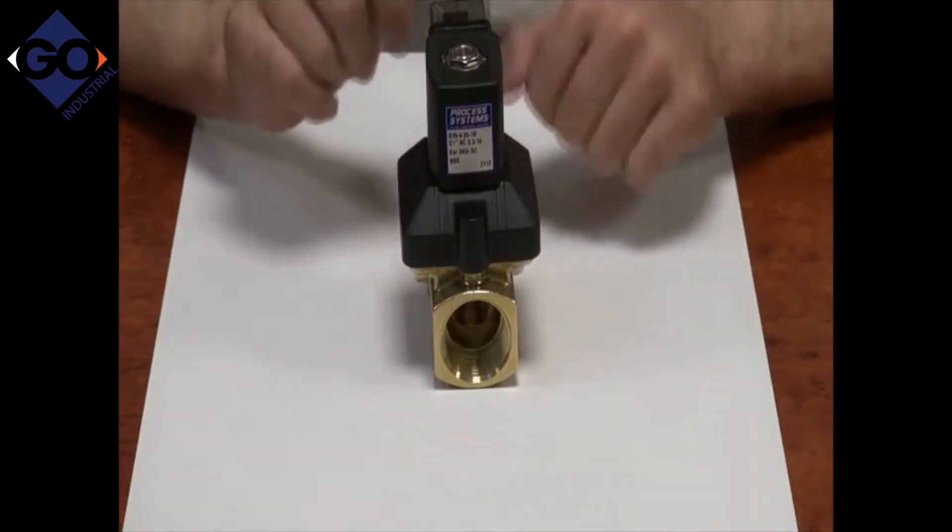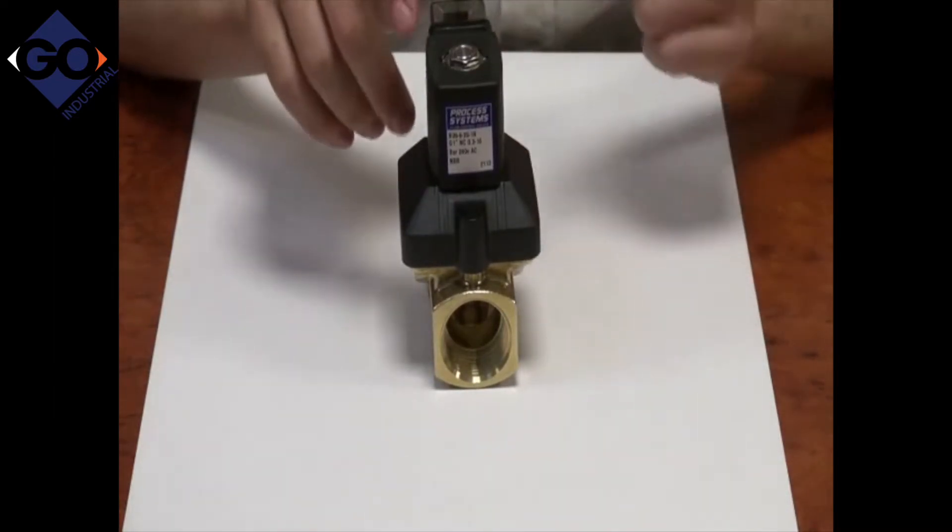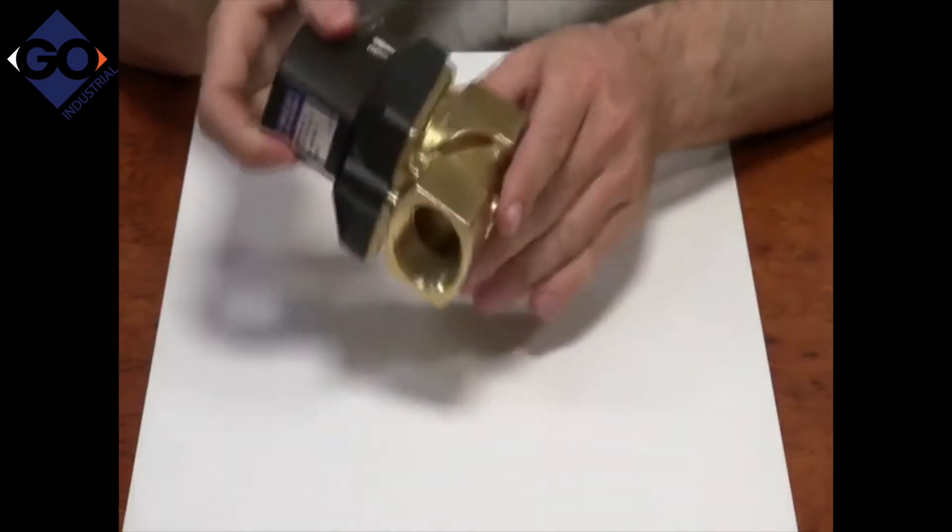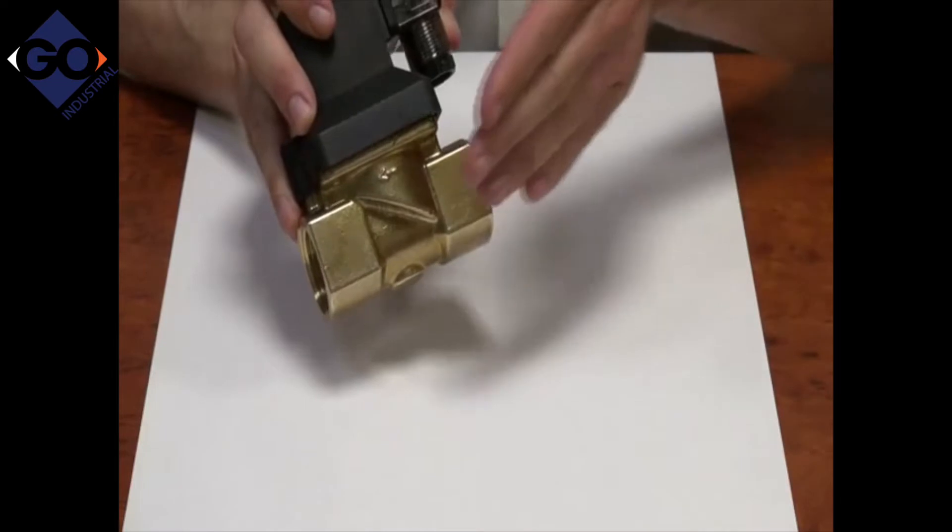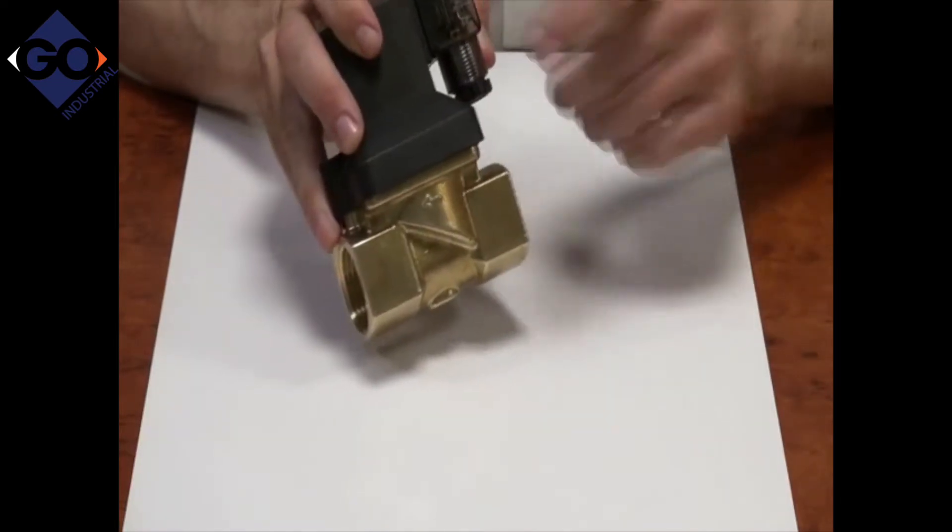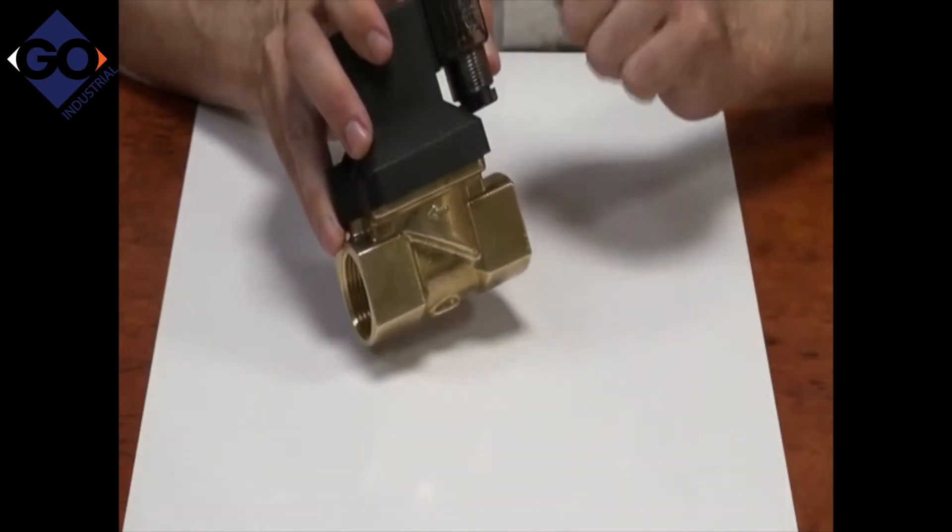Another important feature when installing this valve is the direction of flow. If you look on the side of the valve, it has an arrow. This is the flow direction, inlet to outlet. If you put it around the other way, the valve will leak and won't work.